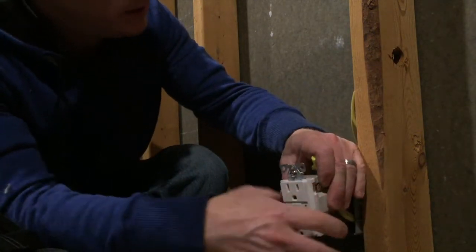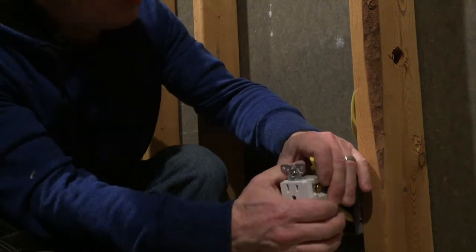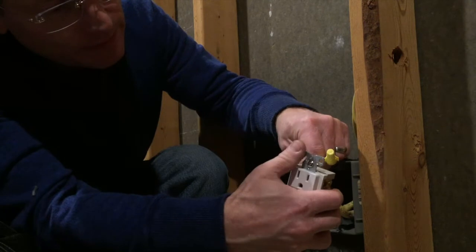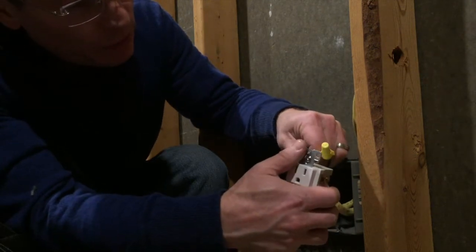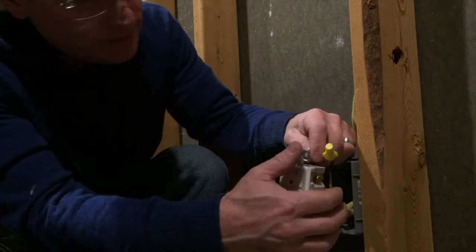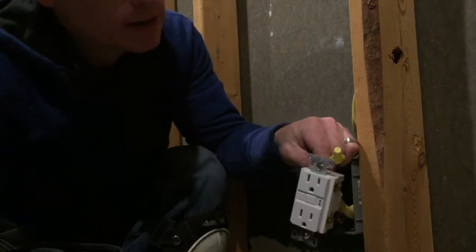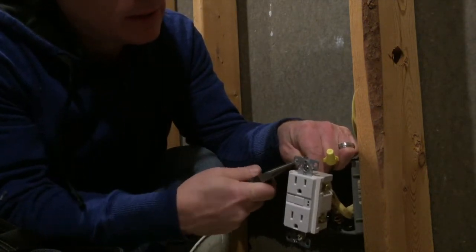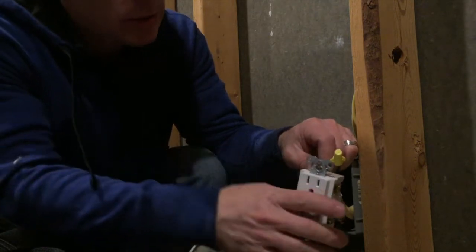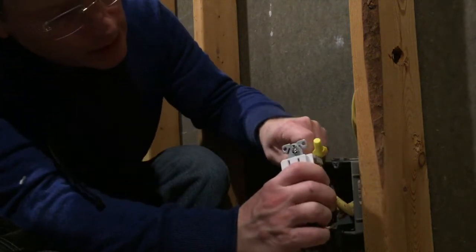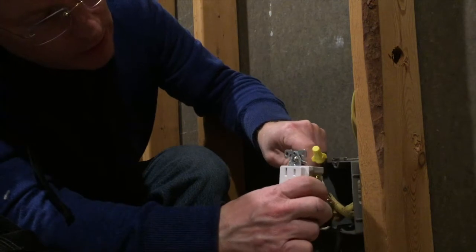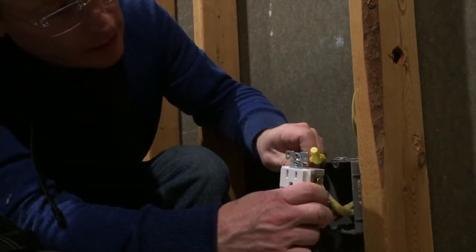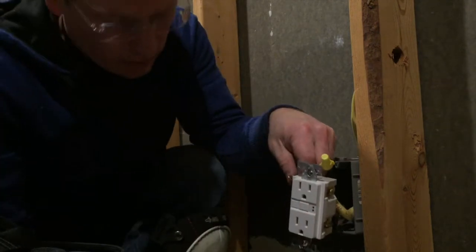I see these wires were stapled to the wall with metal staples. So if one of these staples hit one of the wires, then that could be my short. But I don't know which span of wire it is, and there's a lot of staples. So I just got to narrow this down and then try to figure out how to get the short circuit out of the circuit.